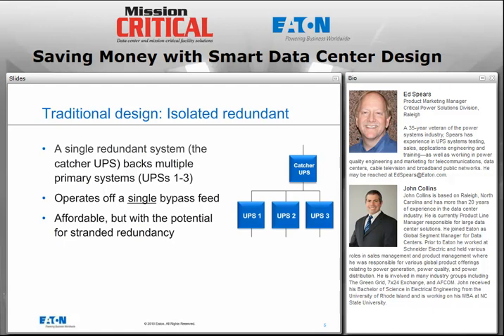And again, this is traditionally deployed in a one catcher per UPS or up to a one catcher per 3 UPS. So this way you get some redundancy without having to make, in this case, 3 separate parallel redundant systems. For example, if I wanted to do traditional N+1 UPS paralleling, I would need 2 UPSs to form what is currently UPS 1, so UPS 1 would have redundancy. I'd need another 2 UPSs to form UPS 2 and another pair to form UPS 3. That would be a total of 6 UPSs, half of which are basically not needed to support the critical load in normal operation, along with their batteries and maintenance contracts and floor space and PI switchgear and all those kind of things. So a catcher system, as you can see, provides a great level of redundancy, but only uses 4 UPSs in this case. So it can provide some significant savings. So it was very attractive to use this type of system.